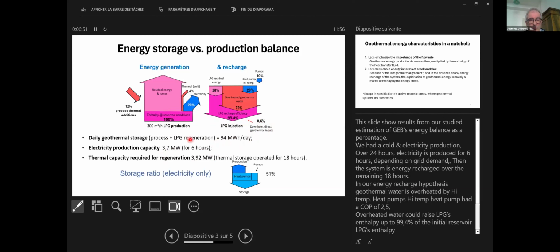So we got this number, an energy production of 3.7 megawatt for 6 hours, because the usual number given by hydroelectric production in France is 4 to 5 hour generation. So we calculate with 6 hours and with 18 hour time for the recharge.